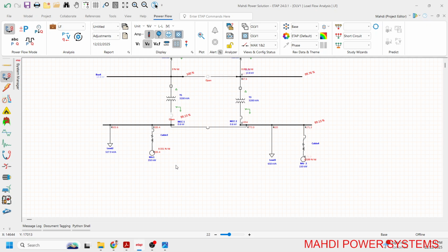Protection coordination always starts from the lowest level of the system. That means we start with the motors, then motor breakers, then couplers, and finally the incomers. Before touching any breaker or relay setting, we must first understand motor starting behavior, how the motor accelerates.